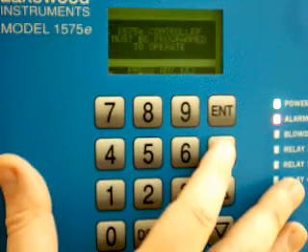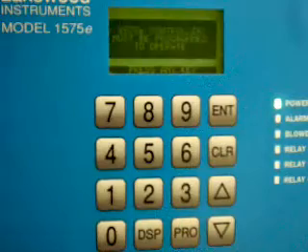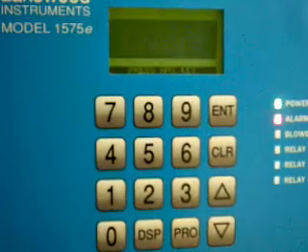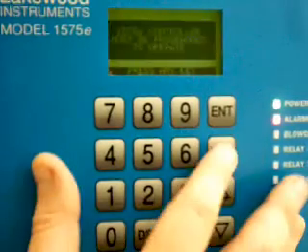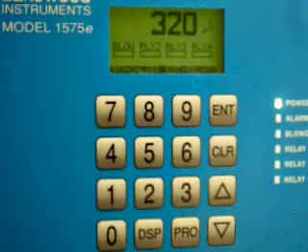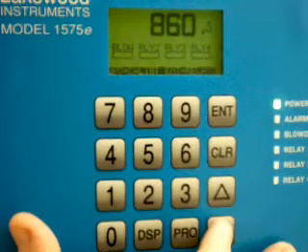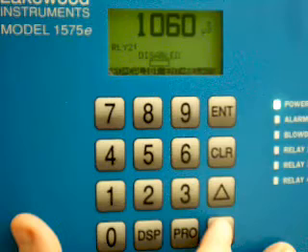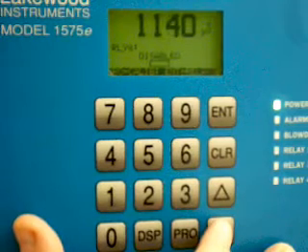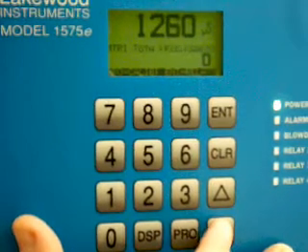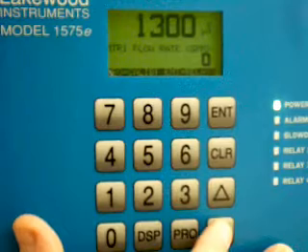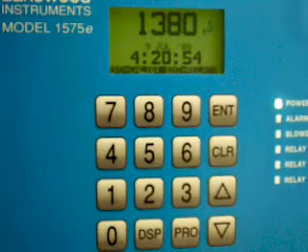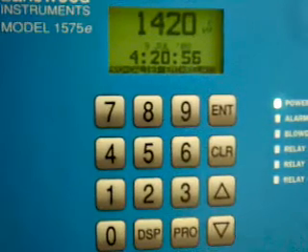Hit clear, and you go back to your first warning screen which says you need to program this thing. Okay, so now it's going to read the raw value, and now if you'll notice, the only thing that was saved was the time and date. All the relays have been disabled, all the water meter counts are reset. Time and date was saved, but that's it. Everything else has been reset.